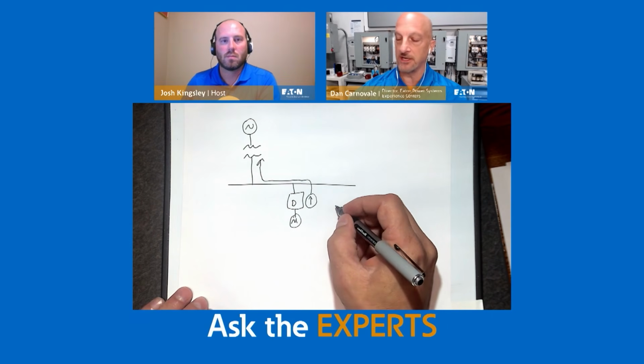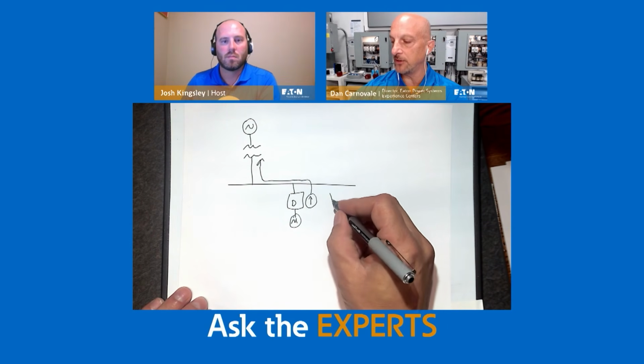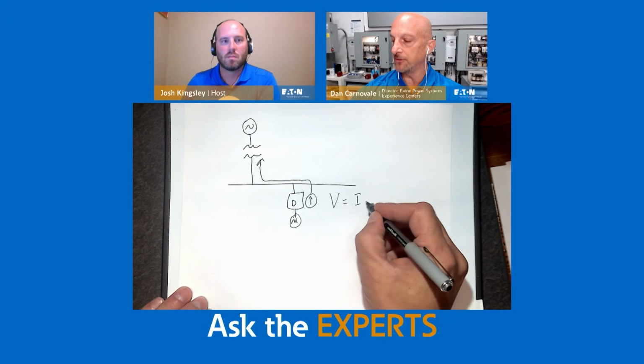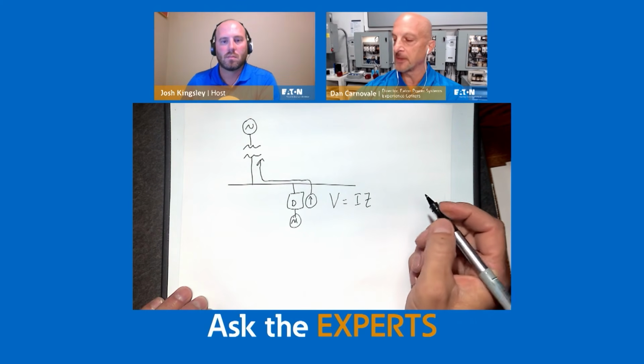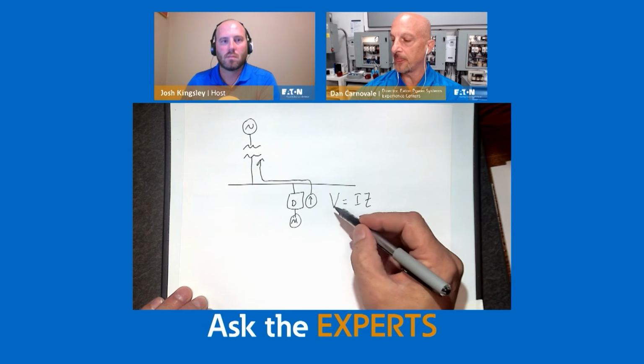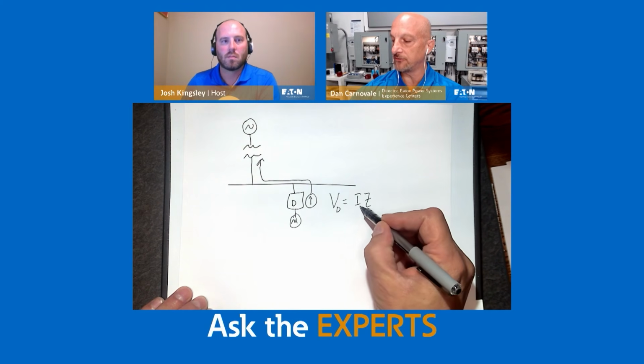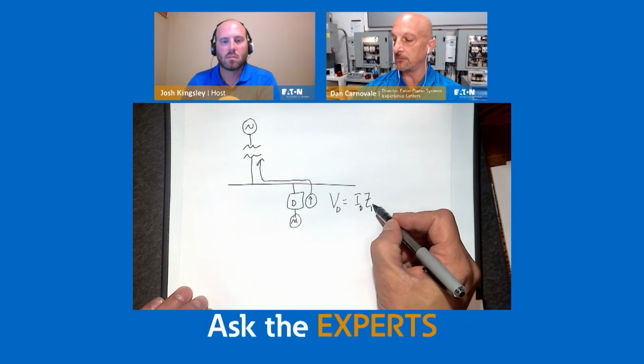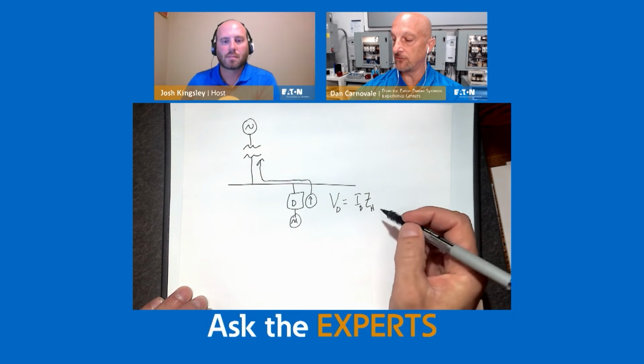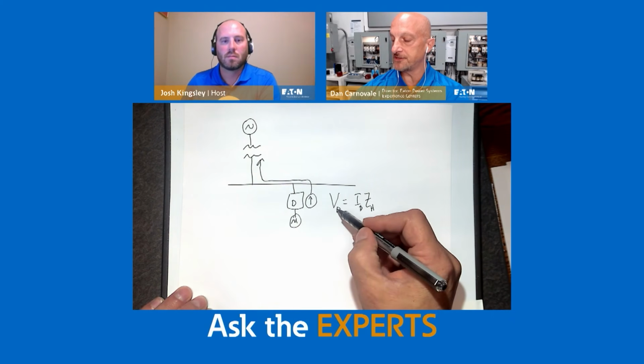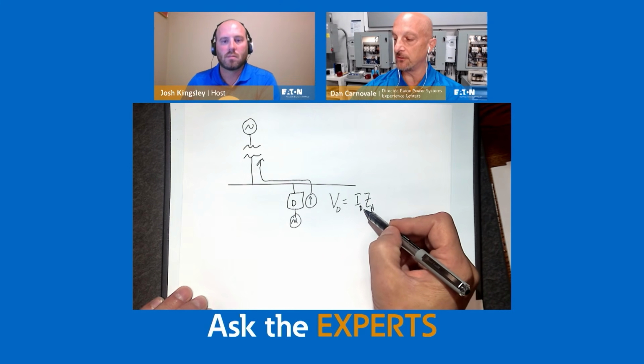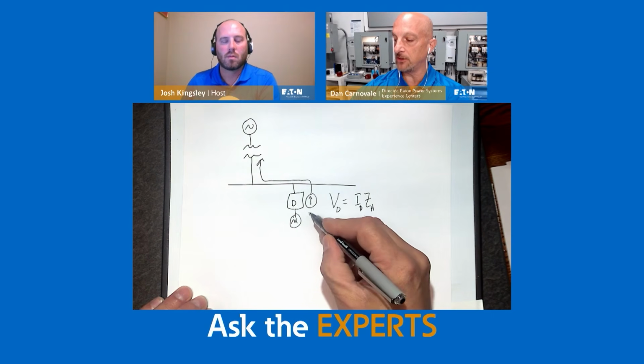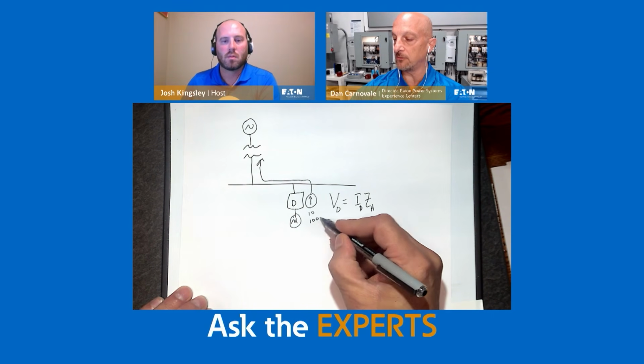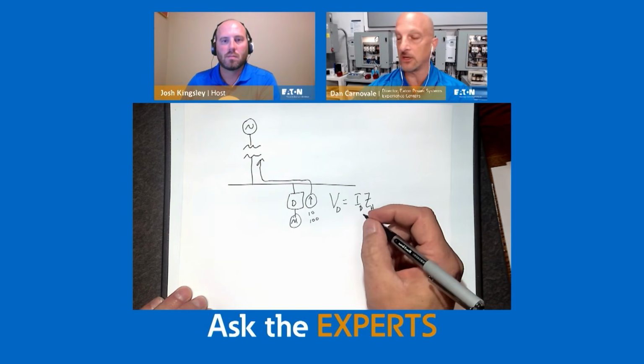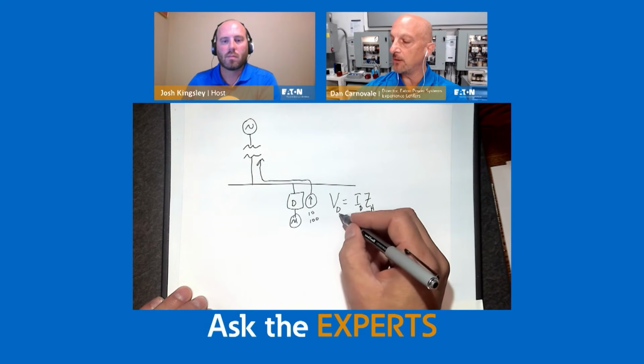Now, what's really interesting about harmonics is it seems overly complicated, but it's really just Ohm's law. Voltage equals current times impedance is Ohm's law. And when we start without the drive, we have an equation that looks like this. Voltage distortion equals current distortion times harmonic impedance. Basically for the first scenario where we don't have a drive, voltage distortion equals 0 because current distortion equals 0. But as we add more and more current distortion, in other words, let's say we go from 10 amps maybe with one drive to 100 amps with multiple drives of different frequencies, fifth harmonic, and again, we'll come back to a little bit of that, we add more and more voltage distortion.